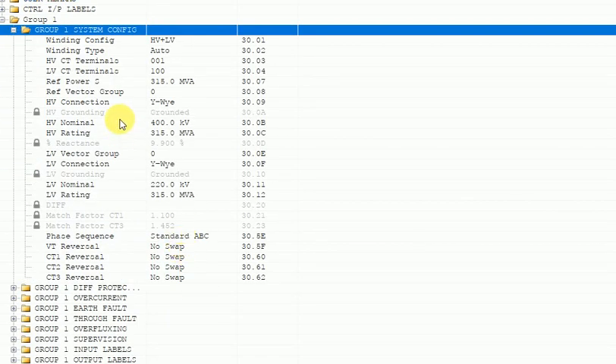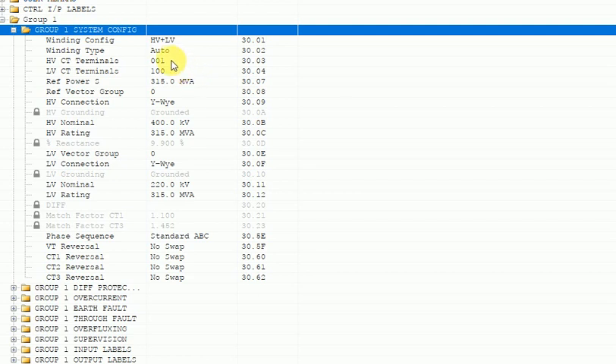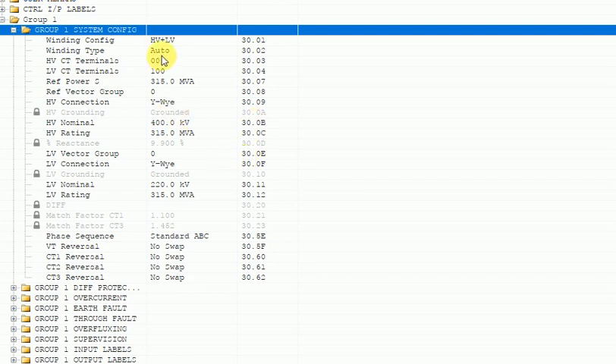Under system configuration, you can see the following parameters: winding configuration, winding type, HV CT terminal, LV CT terminal, reference power, and reference vector group. These are the parameters available to configure differential protection. This will be configured by seeing the scheme drawing — according to what is in the scheme drawing, you have to set these parameters.